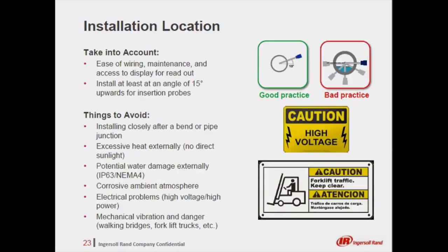Choosing the correct installation location is another important aspect to consider as part of the recommendation process. The flow meter should have access to the power supply and be readily accessible for maintenance and data readout. Insertion probes should be installed at least at an angle of 15 degrees upwards or greater.